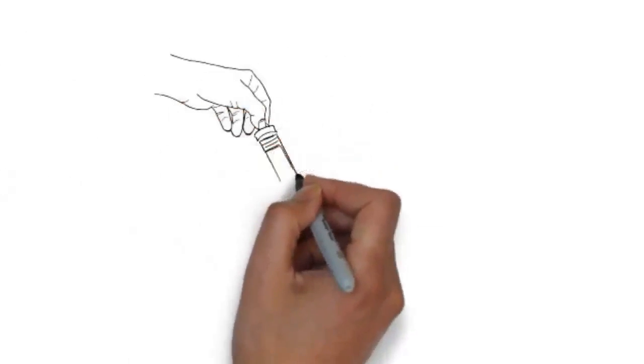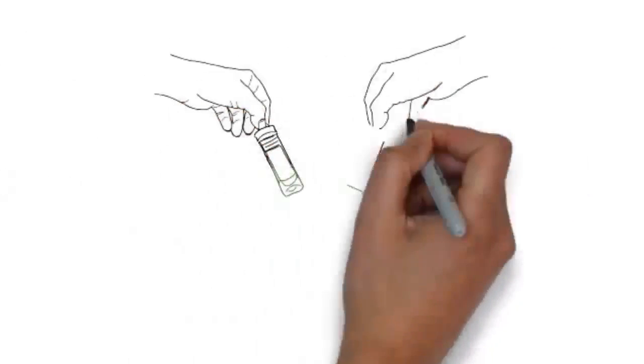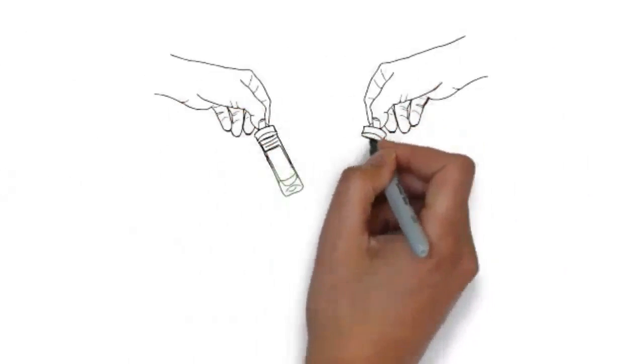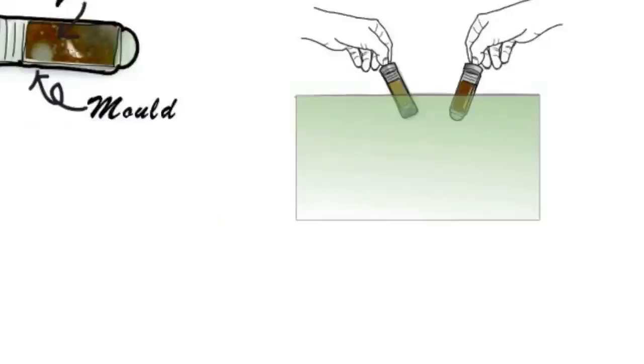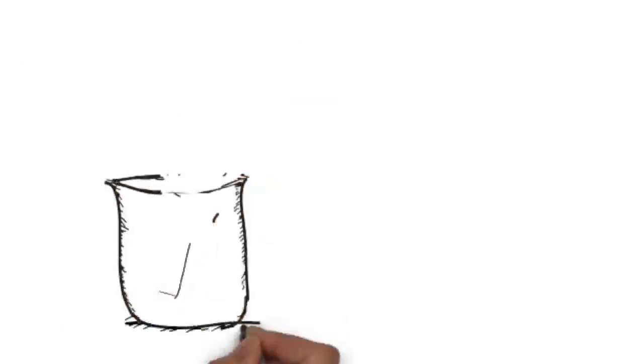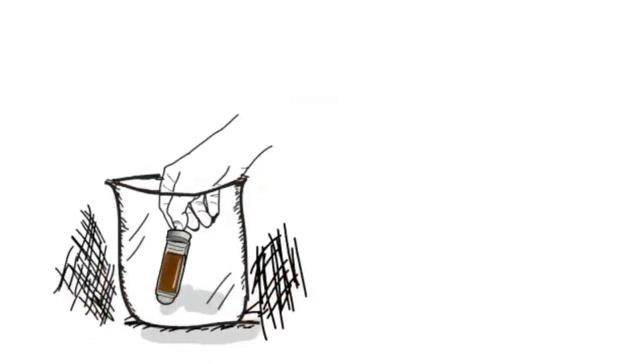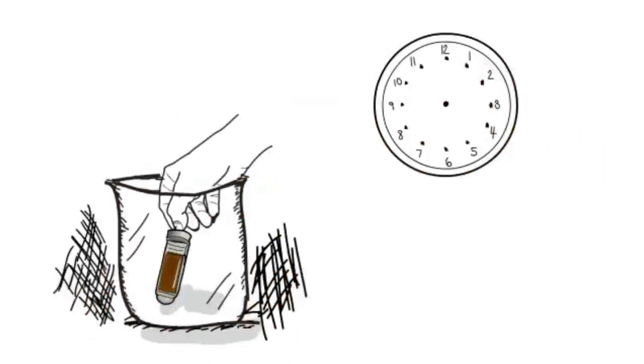To test for diesel bug, simply immerse the test slide into a fuel sample for about 10 seconds, then store the test kit in a warm dark place for at least 24 hours to allow the culture to grow.